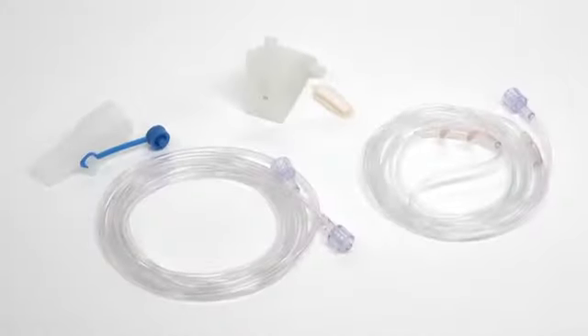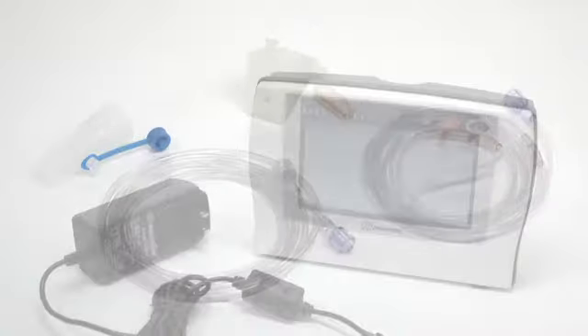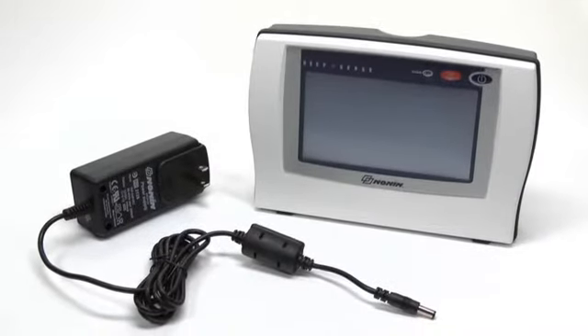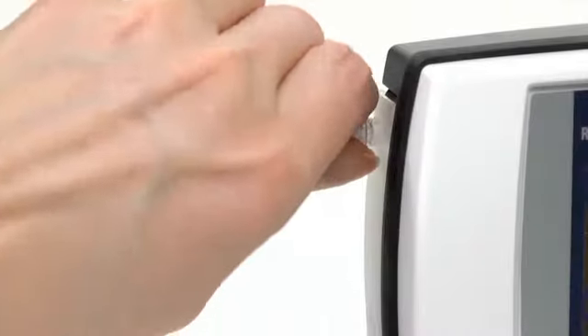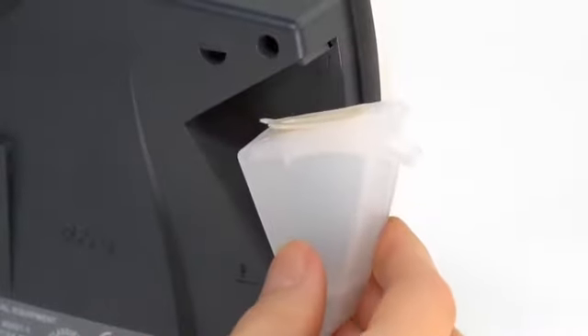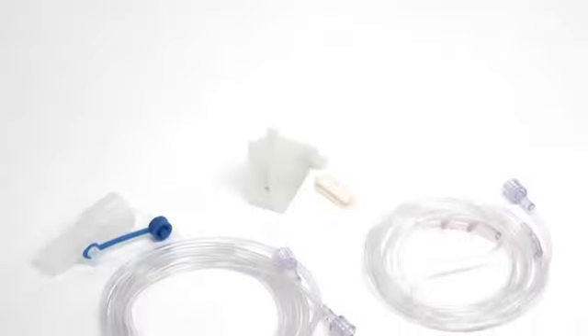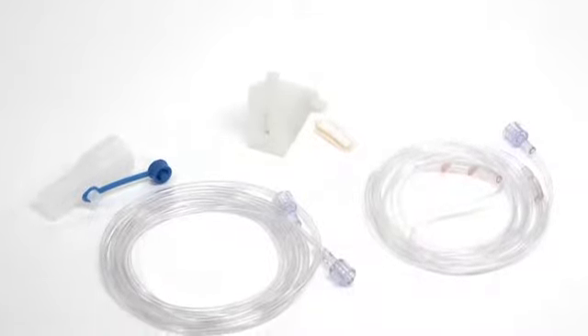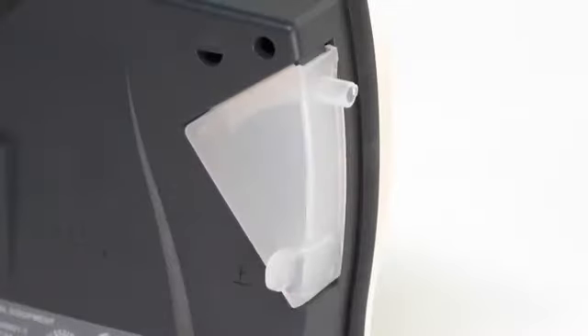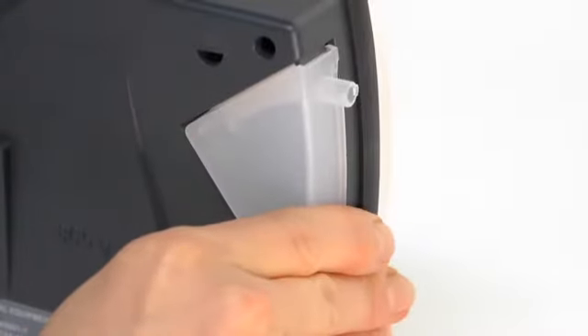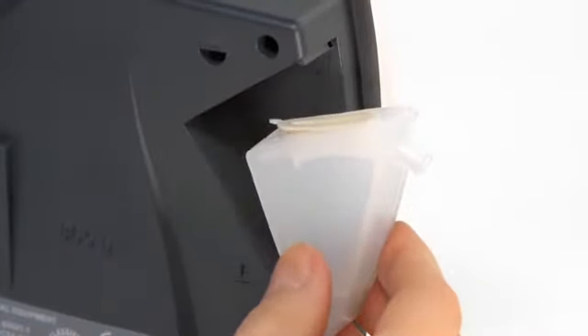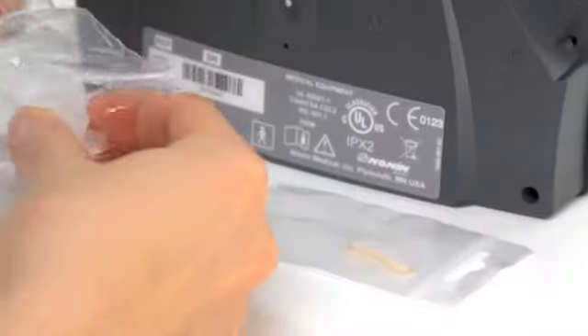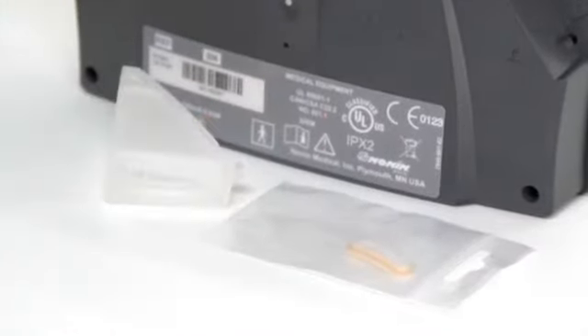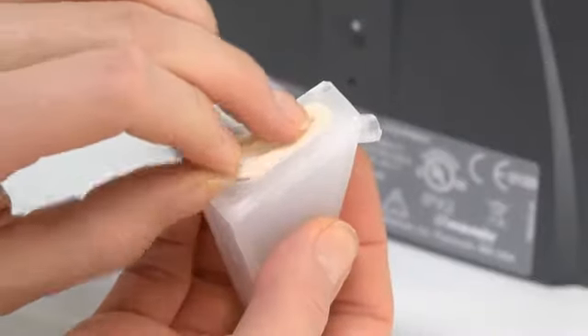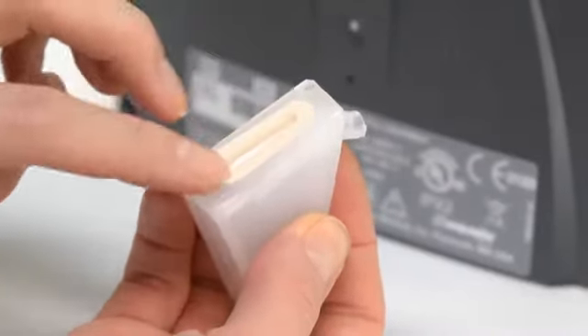Setup consists of a monitor, moisture trap with filter, nasal cannula or T-connector and sample line, and the power supply. Moisture traps, filters, and sample lines are single-use components and disposed of after each patient use. Start each patient with a new sample line, moisture trap, and filter. Remove the used moisture trap from the monitor by pulling on the tab to snap it out of the housing. Then remove the filter. Open the new moisture trap and filter and place the filter into the slot on the top of the trap. Insert the moisture trap into position on the side of the monitor.